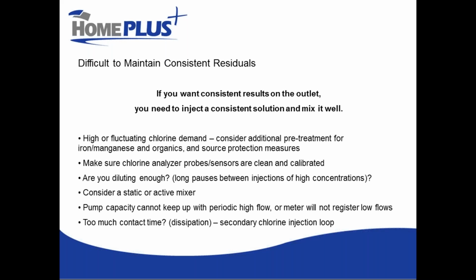But if you do happen to have those parts, they're very expensive, and you want to keep them clean and lasting as long as possible and reading as accurately as possible. If they provide inaccurate feedback to your chlorine pump, you'll definitely get inaccurate results. Follow the manufacturer's recommendations for cleaning those probes and sensors, because they do vary by manufacturer.